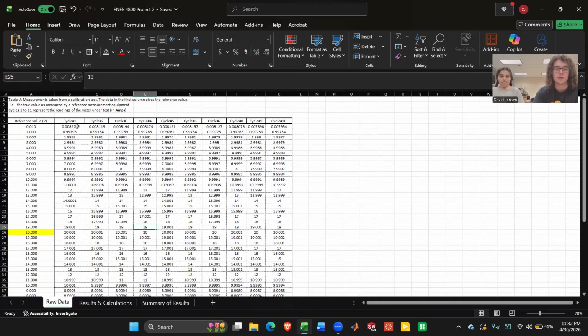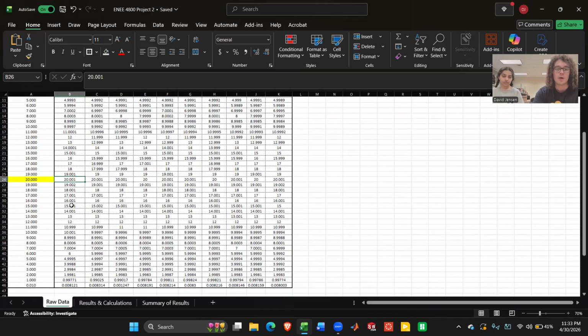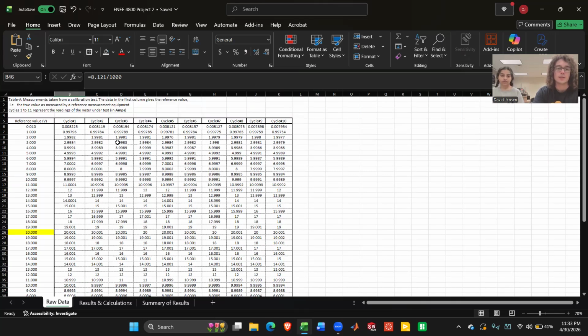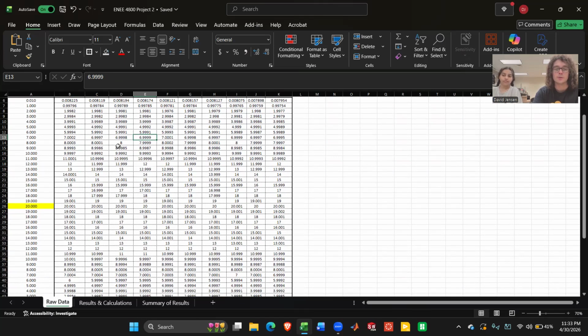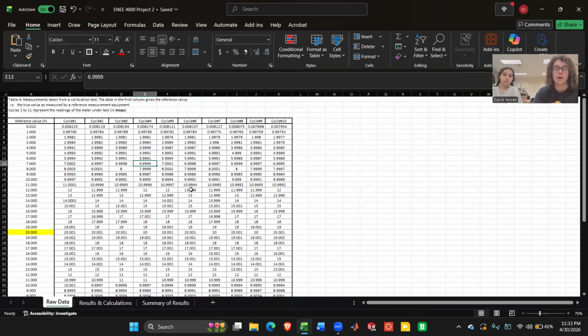And so we're going to look at the first cycle here. We started out with a reference value of 0.01 volts, and we measured 0.008225. We repeated this process for each corresponding reference value as we went through our up cycles up to a peak value of 20 volts, and then we stepped down all the way to our starting value of 0.01, recording values at each step. This aligns with the ANSI standards for the calibration procedure. We repeated this procedure 10 times to ensure sufficient data was collected for the proper analysis of the measurement device.